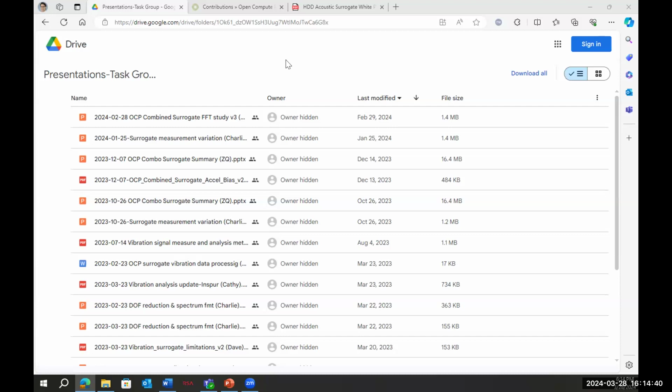Unfortunately, the status is even worse in that the lab lost my fixtures for calibrating this thing, so I have been unable to actually calibrate them. But I do have the documents detailing the process that would have been undertaken, and I thought I put that on here, but I can go back and check. Yeah, would you please? And then whatever you feel comfortable uploading here, that's what I'll reference in the calibration scheme. Yeah, I can do that, definitely. Okay.